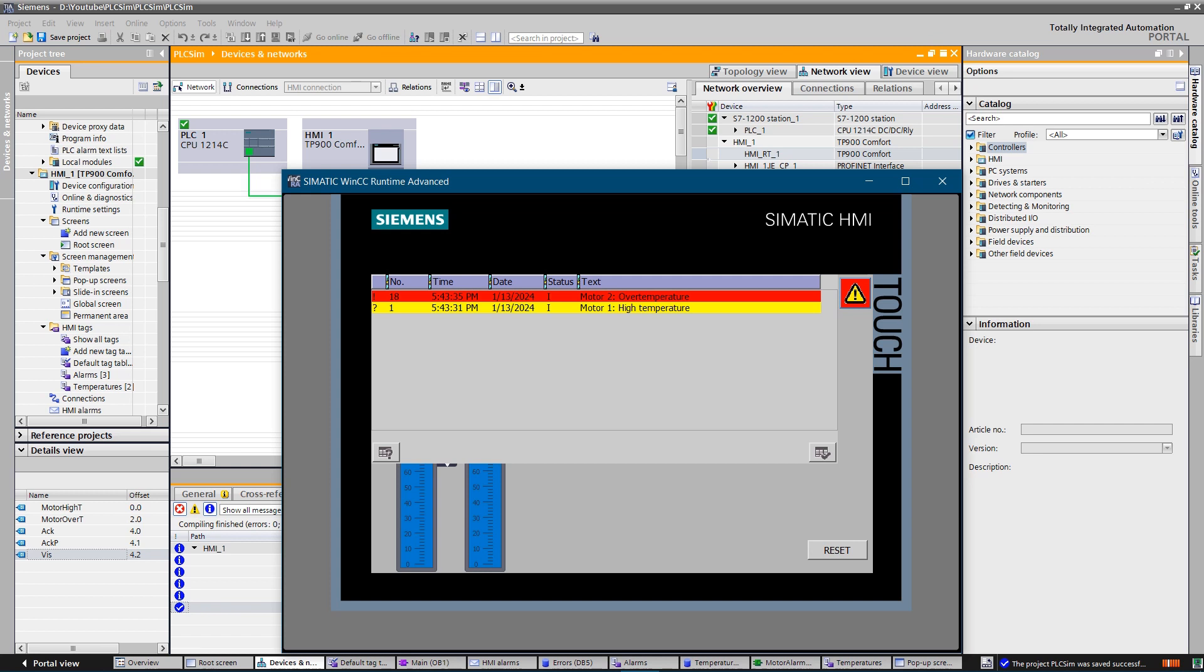Warning is activated when motor reaches temperature of 70 degrees Celsius. By getting a warning, operator also gets a message on actions needed to be taken into account. Motor will not be stopped when warning occurs.